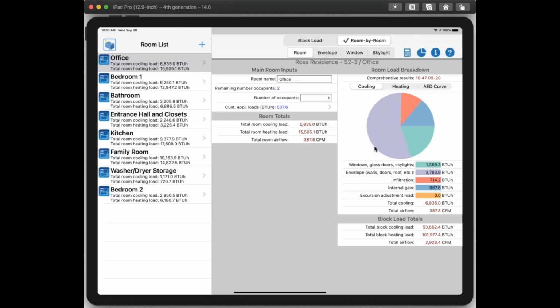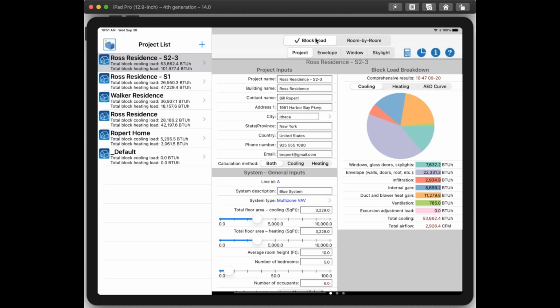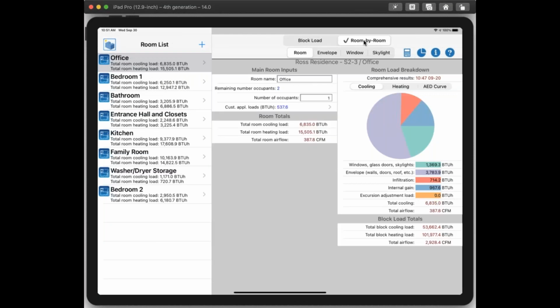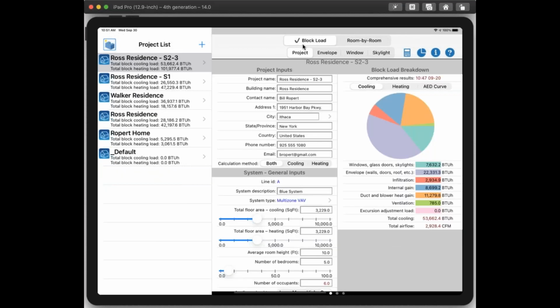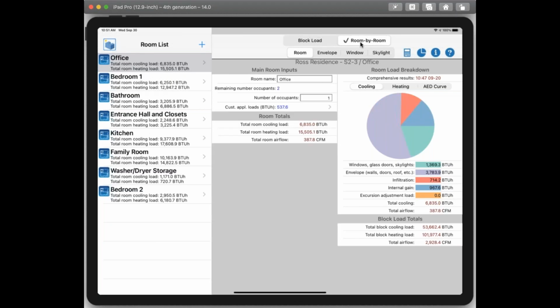We get this question all the time: how come the total of my room by room load doesn't equal my block load? Well, it will never equal your block load unless it's a total coincidence, because rooms peak at different times of the day, so the sum of the peak loads is never going to equal your block load. If they are equal, they probably shouldn't be. Most of the time, the total of all your room loads will be greater than your block load, because we're totaling all the peaks. A room facing east will peak in the morning, while a room with west windows will peak in the afternoon, so those loads peak at different times of day.